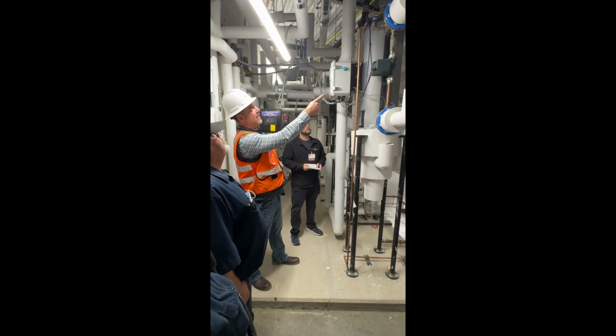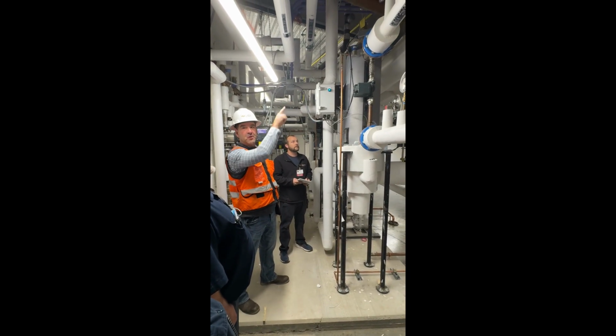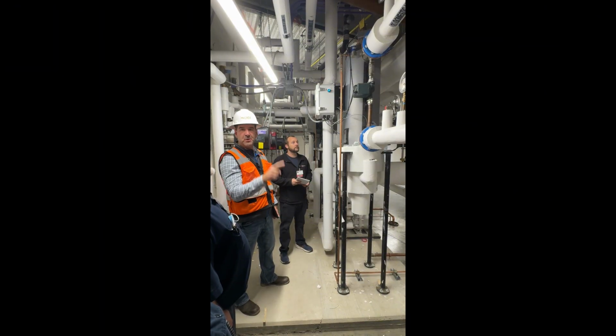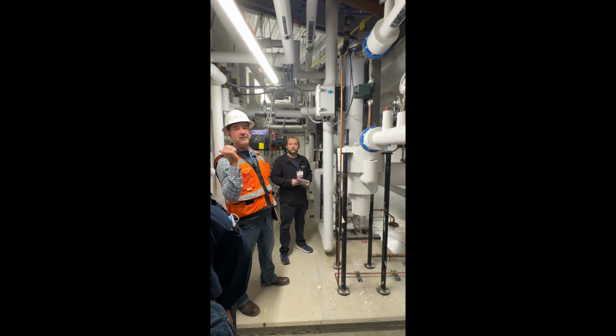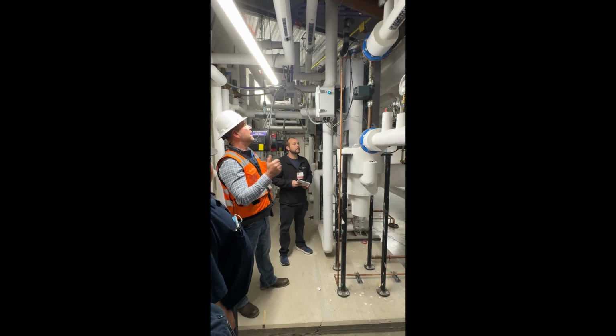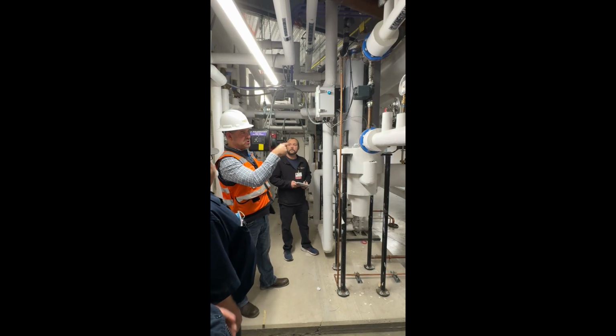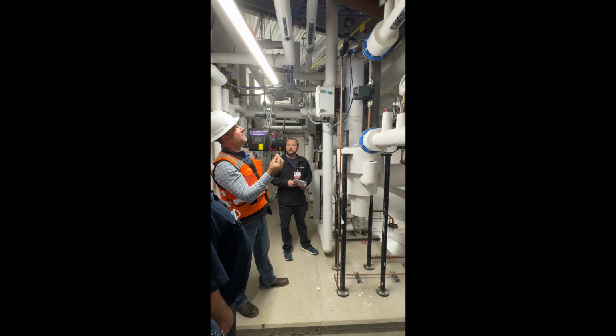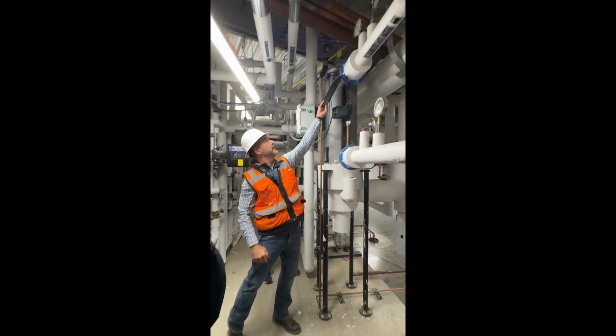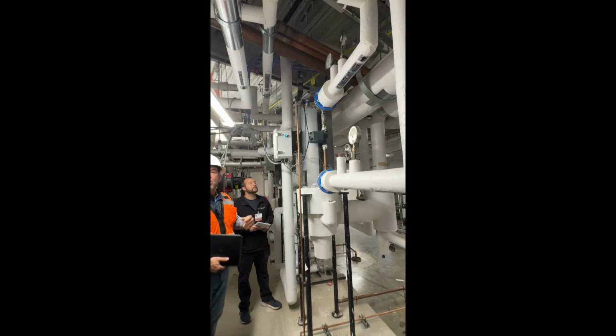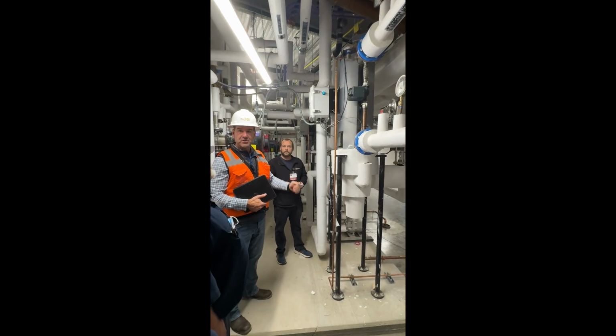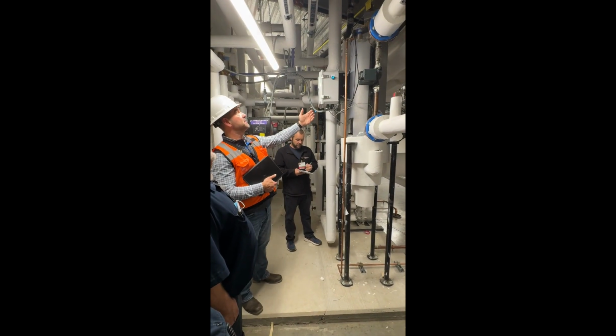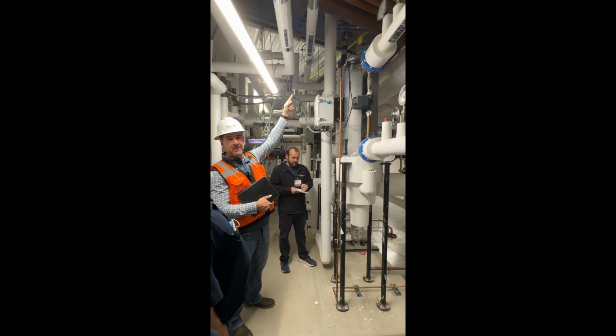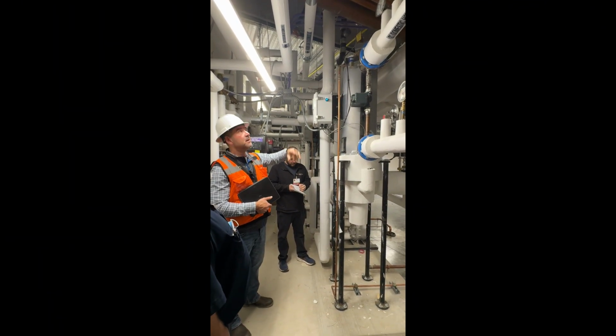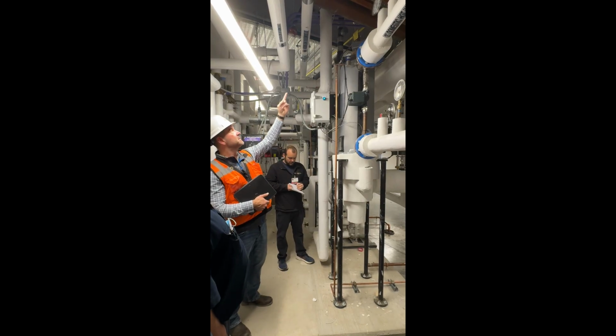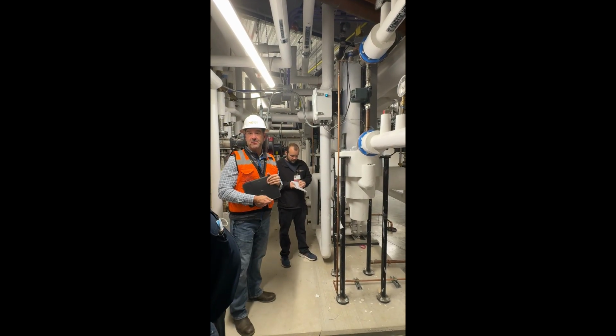We do have a circulating pump. This is just for internal stratification. All that's doing is making sure you get a good mix. It doesn't do anything on the system. If for whatever reason we do overtemp, there are two safeties. One is a solenoid pop-off valve, which is right up here. When that temperature drops back down, that'll actually close. If it keeps increasing over, we actually have a relief valve on the top. That's a manual reset. So the solenoid one is an automatic reset. The PRV is a manual.